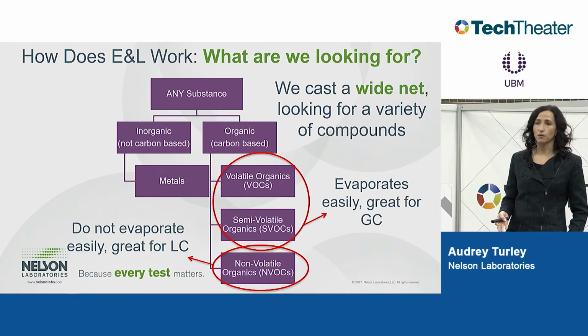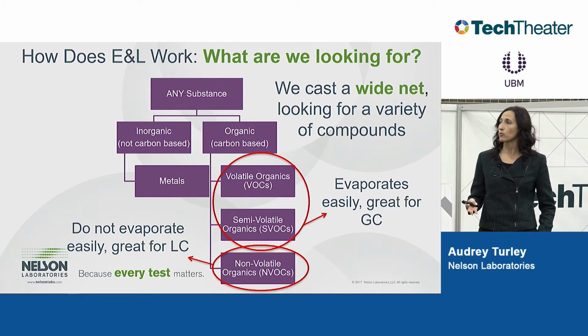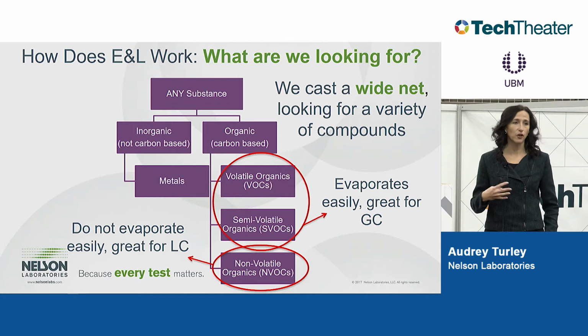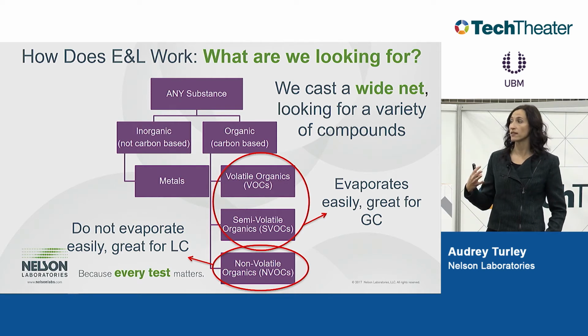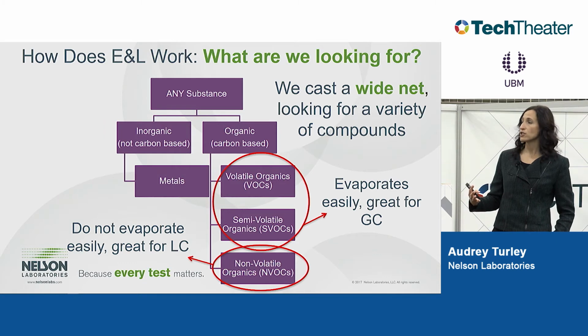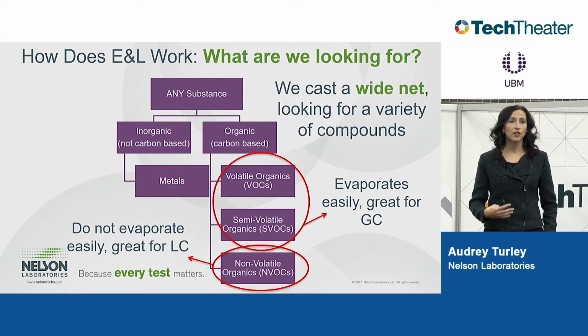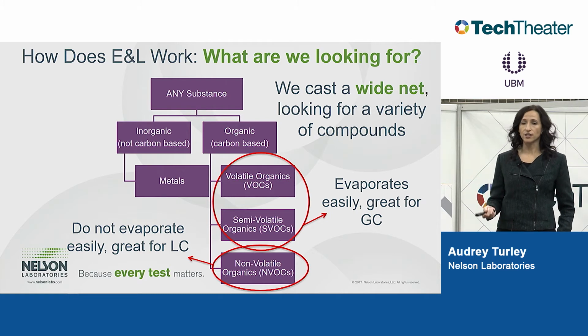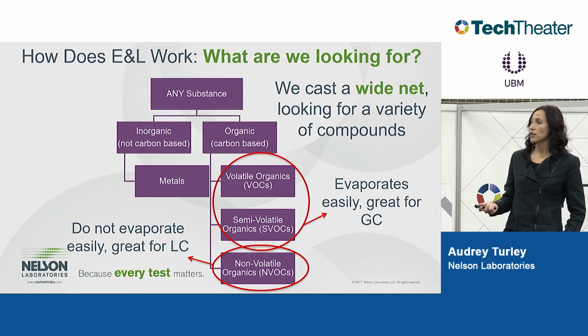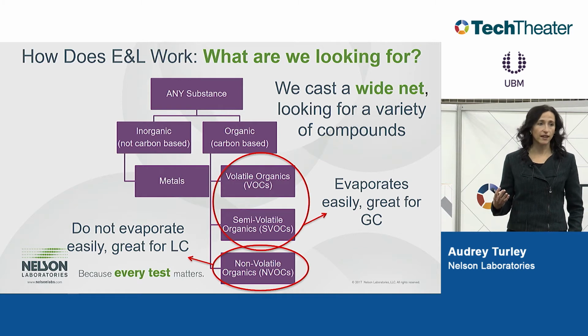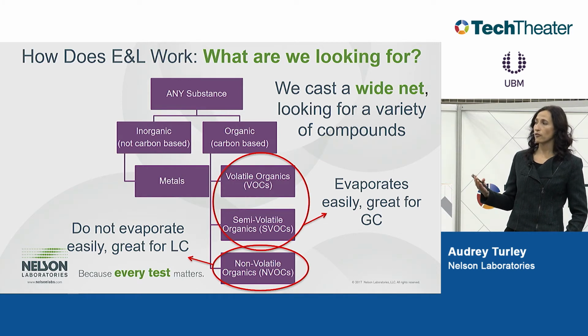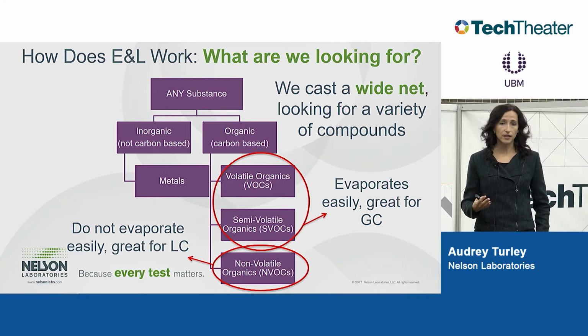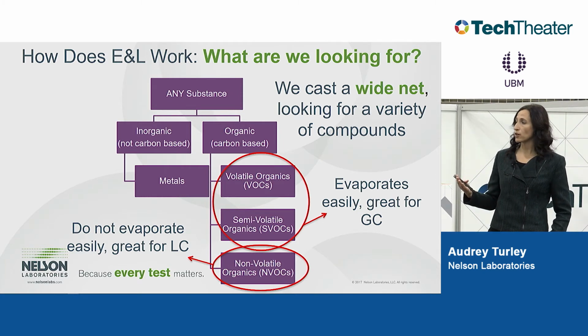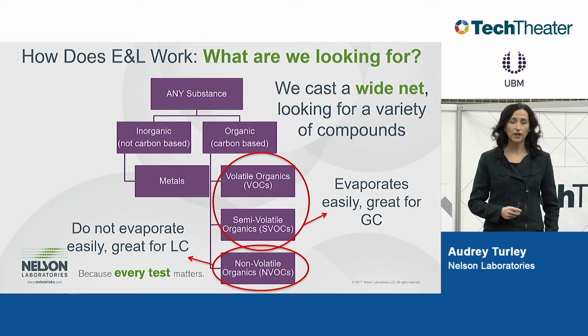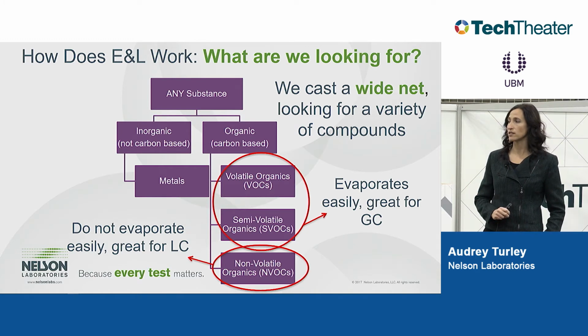So what are we looking for when we run these extractable and leachable tests? We really cast a wide net, analyzing for anything we can find in the condensate or, in this case, the extraction. So we look for inorganics, which would be metals, and then organic compounds, which would be our volatiles, our semi-volatiles, and our non-volatiles. For the organic compounds, the separation is really size-based. If you have volatiles and semi-volatiles, we'll use a GC, gas chromatography, because those are smaller and they will evaporate. And then for non-volatile organics, we do use an LC, liquid chromatography.